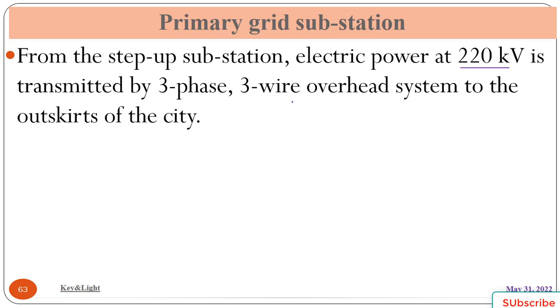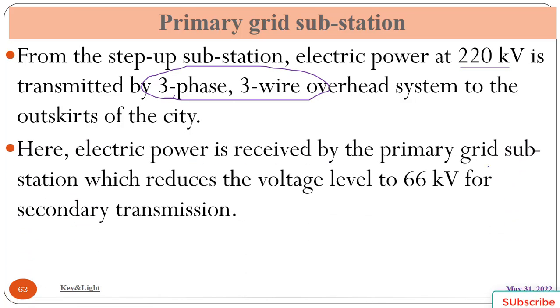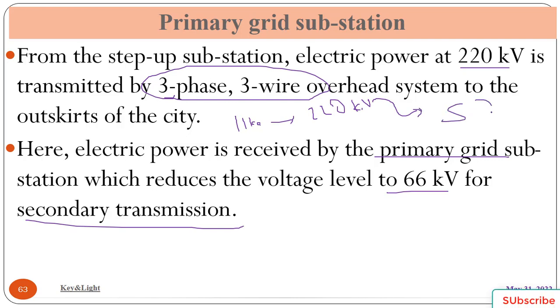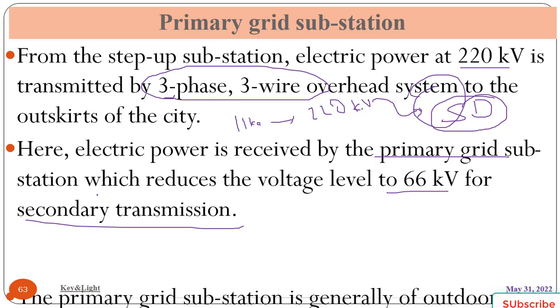The next one is primary grid substation. From the step up substation, electric power at 220 kV is transmitted by three-phase, three-wire overhead system to the outskirts of the city. Here, electric power is received by the primary grid substation, which reduces the voltage level to 66 kV for secondary transmission. A system is said to be primary grid where it receives the first stepped up voltage. In this case, 11 kV is generated at the generation station and stepped up by a step up transformer to 220 kV, and it gives to the step down substation, and this first step down connection is said to be the primary grid substation. The primary grid substation is generally outdoor type.